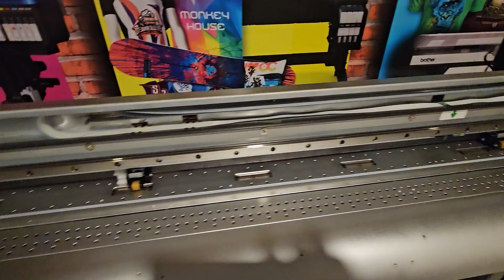It's doing its aging. Another thing I'd like to note, I just had a guy that contacted me about a scan motor error, and all he had to do was run a simple limit initialization, which I have another video on, so make sure you check out that video. Do a limit initialization, make sure that isn't causing your grief. But that's pretty much it when it comes to scan motor errors.